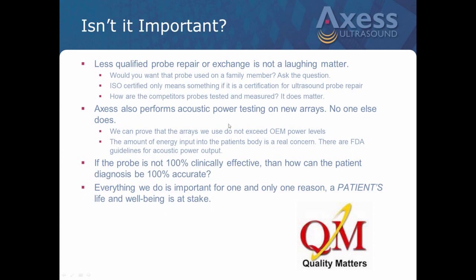Is it important? Well, of course it is. When you're looking at repairing or exchanging probes, make sure that you ask yourself a few questions. Do you want that probe used on yourself or a family member? That's something we use here all the time, especially when our probes go out. That question is asked. ISO certification, I'm a big proponent. Make sure that you're certified. Your companies you're using are certified in 13485 device probe repair specifically. And the big one is, how are your suppliers testing and measuring the performance of the probes you send them, because it truly does matter.